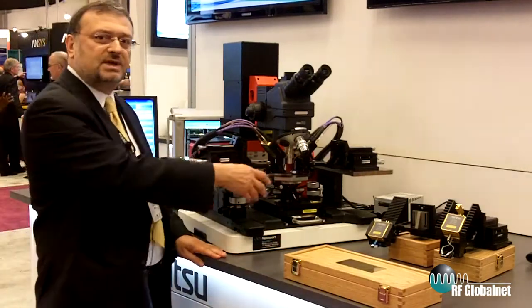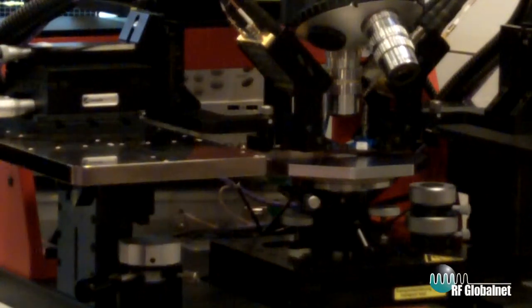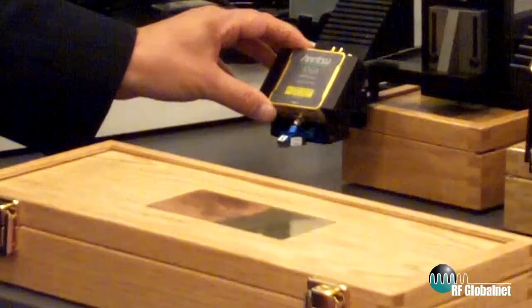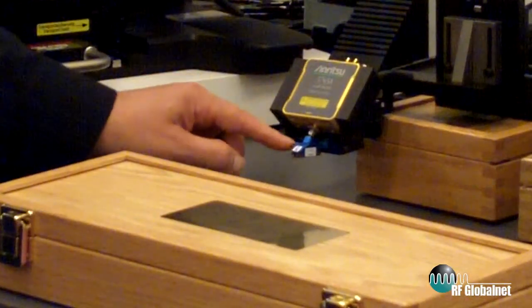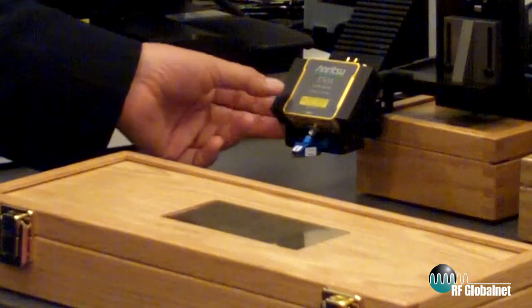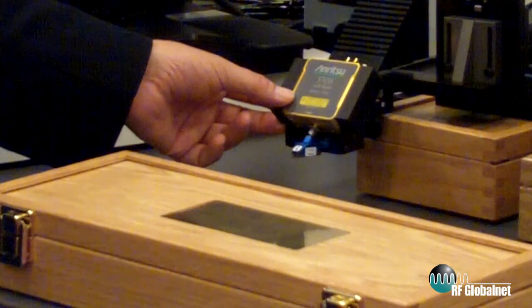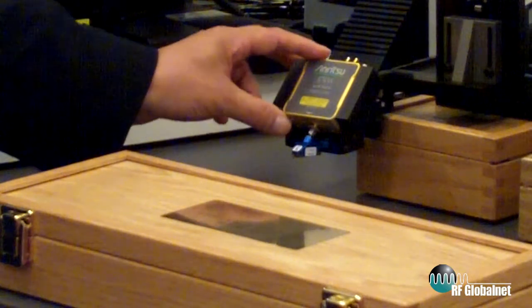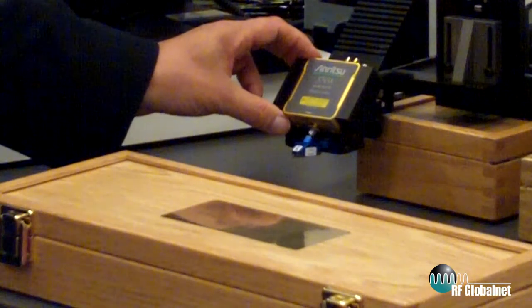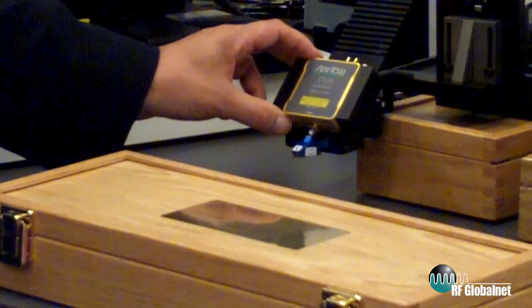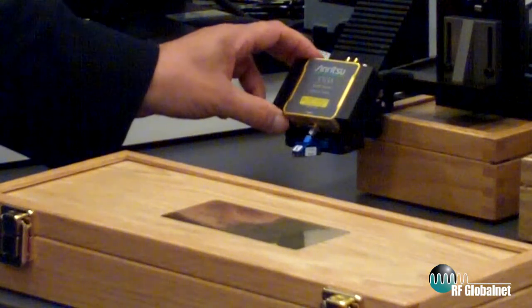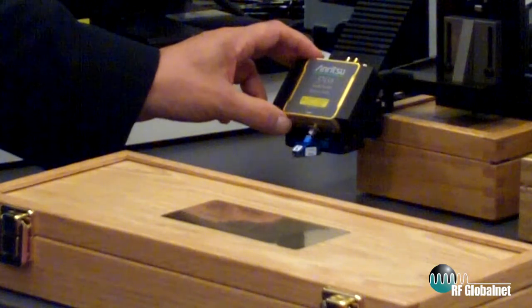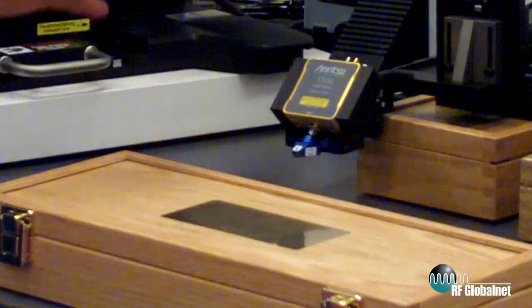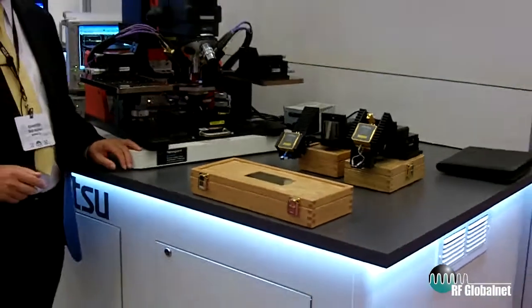What you see here is a demonstration of on-wafer probing. Last year, we introduced the world's first very compact on-wafer probe test heads that allow direct connect with the probes themselves. These operate from 40 kilohertz to 125 gigahertz, and they were first in being so miniaturized, but also having leading stability, requiring only calibration to be done once a day, and improving dynamic range by 20 dBs in the area of 110 gigahertz.